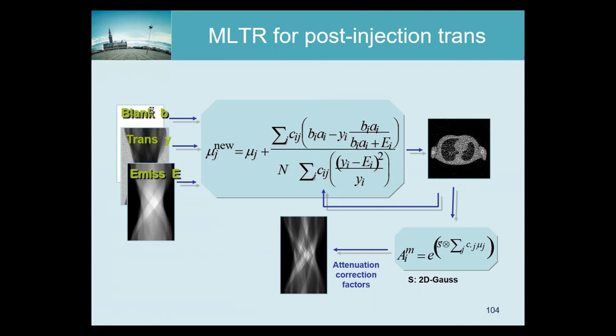Here is the new algorithm. Now we have a blank scan, a transmission scan, and also an emission scan — either just before or just after the transmission scan — and all are inputs to the algorithm. The emission scan goes in as an additive contribution. Using the electronic window, we know that only a few percent of the emission activity can actually get into the transmission window, because most will be rejected. So we can account for that contribution. We iterate, and the longer we iterate the more noise we get but the better the resolution. Forward projecting produces either the attenuation values or the attenuation correction values.